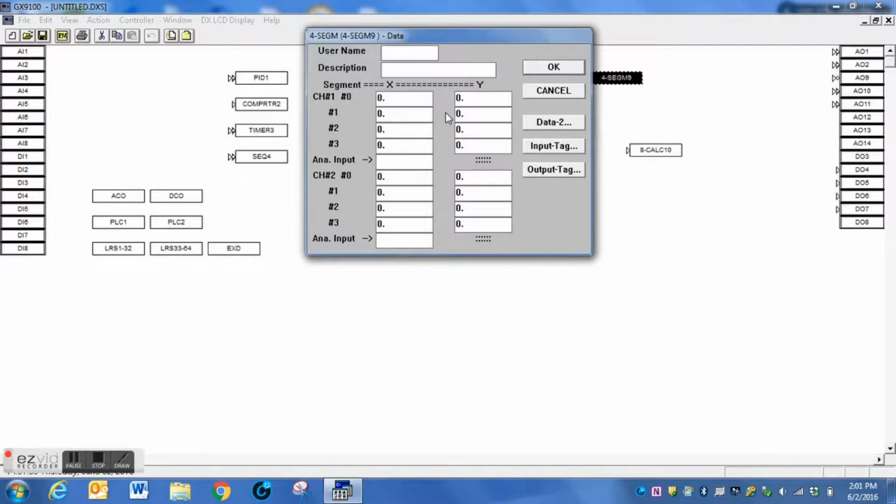Now then, we're going to be using 2 of the channels within this logic block. It contains a total of 4, but we are going to be using only 2 of them. The first channel is going to control our original 1/3 valve output. It was originally just a single output. It is now going to be the 1/3 valve output in this system. It's our first valve. We want this system to control that first output from 0 to 50% of the output of that PID loop. And once that PID loop reaches 50%, we want the output itself to be at 100%. We want to have a full 10 volts going from the first output to our valve.